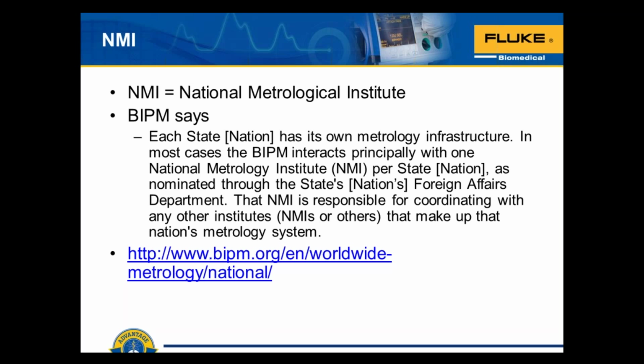And on the other hand, when you just get a brand new DMM or electrical safety analyzer from Fluke Biomedical, for example, that traceability of that calibration is through Fluke Biomedical directly to SI, and I'll talk to you a little bit about how that works, or through an NMI here in the US, which you're familiar with, which is NIST. So it's NIST traceable. We have both, and I'll show you why we have both in just a minute. But that helps you understand the role and responsibility of the National Institutes of Metrology around the world.